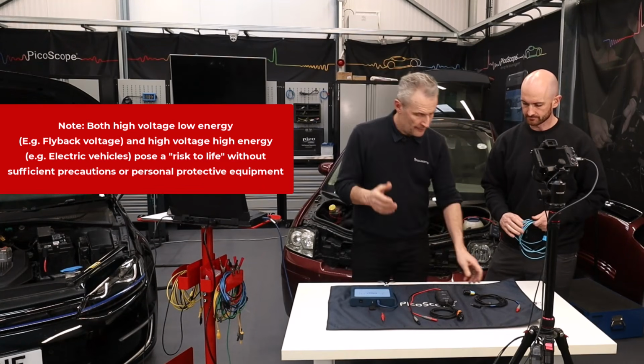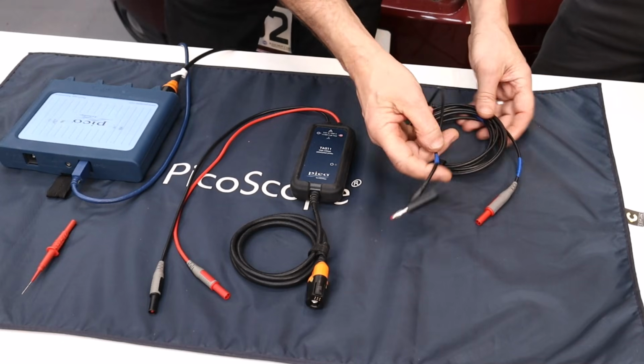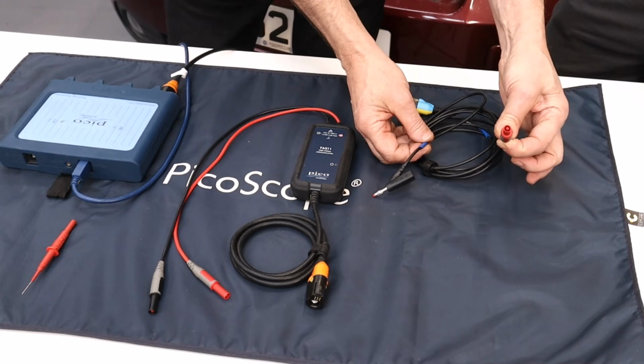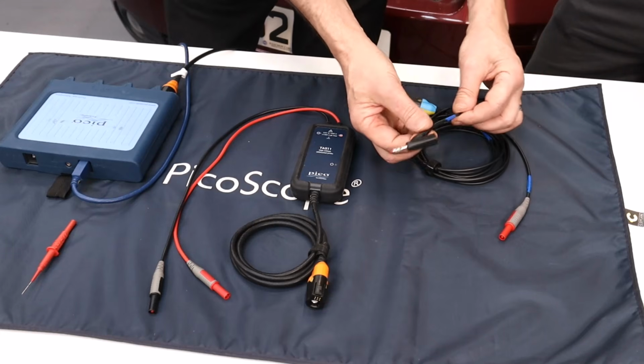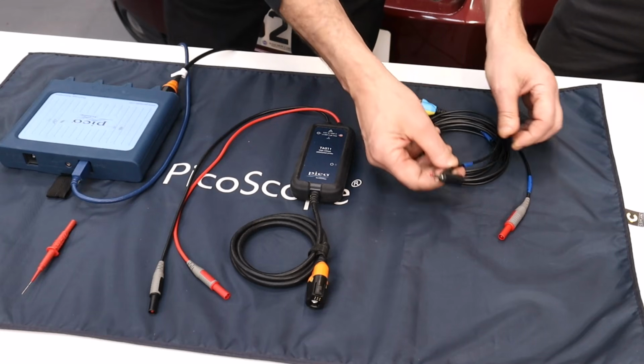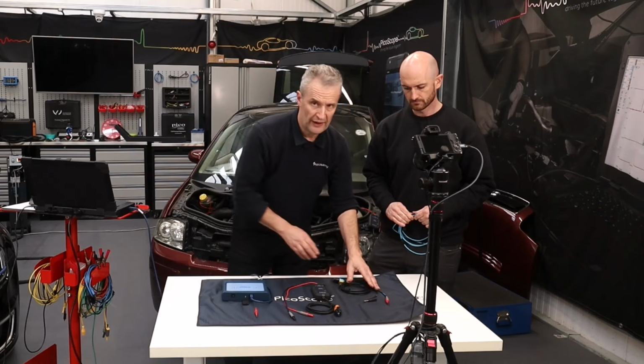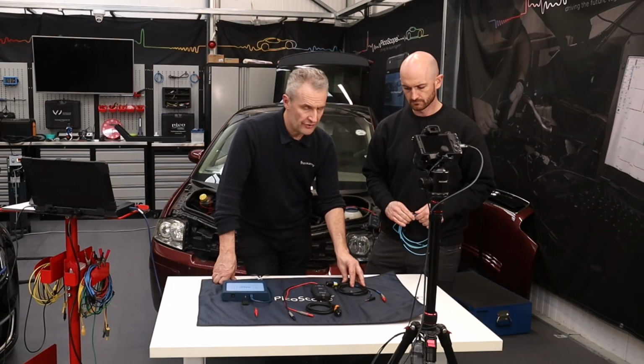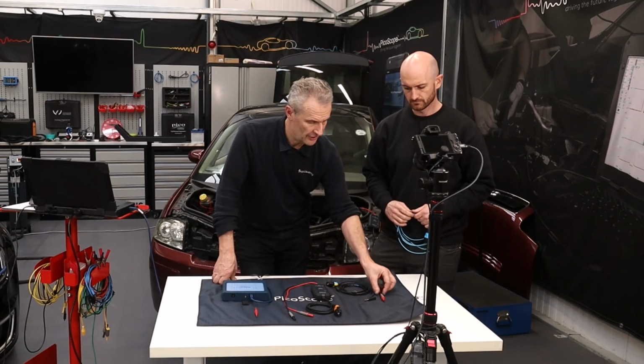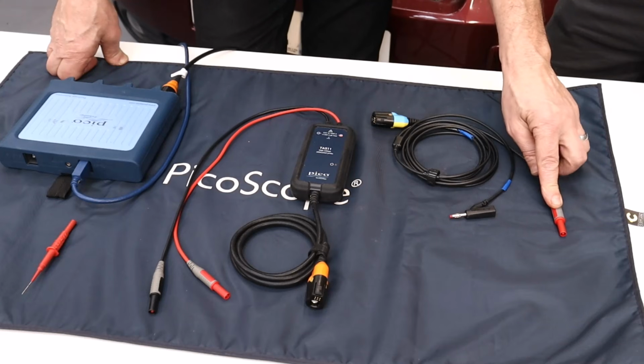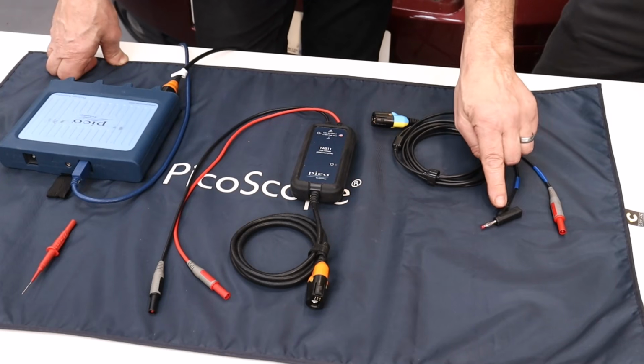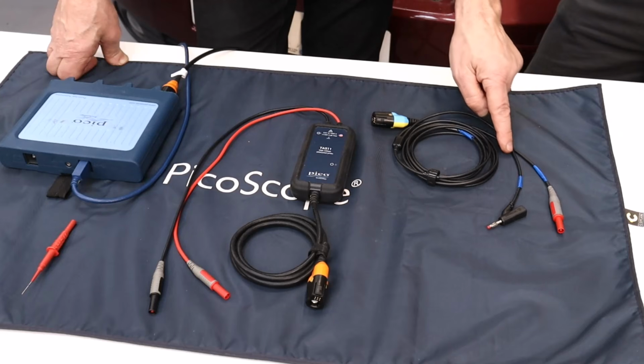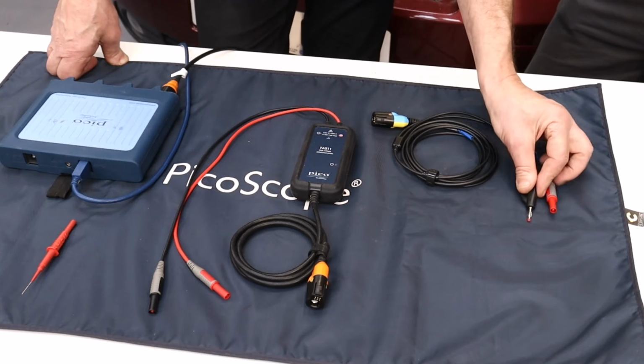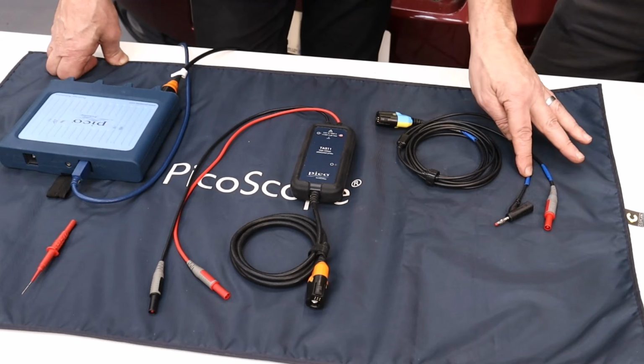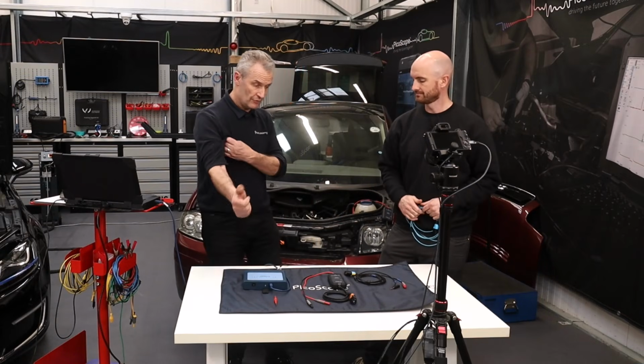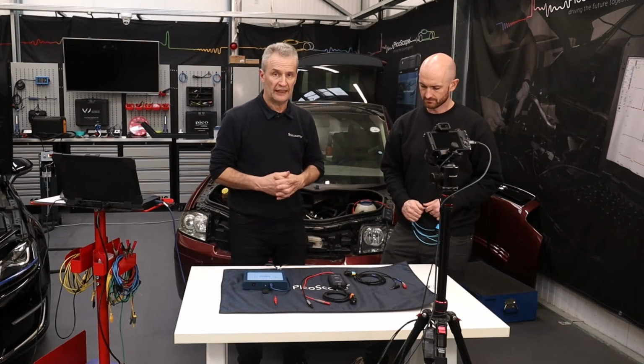So I must also add here that whilst this signal wire, the red lead, is attenuated, the ground lead is not. Okay, so how could that affect what you're measuring? Well, imagine if you were measuring across a high voltage component. The signal wire, the red, is attenuated. However, if there was high voltage passing through on the ground wire, because you weren't measuring reference to ground, you were measuring across a high voltage component, AC, like, exactly, in which case, there'd be no attenuation on that ground.